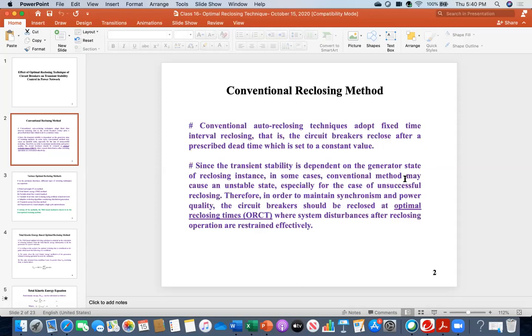Unsuccessful reclosing means the breaker attempted to reclose, but it was observed there was a permanent fault. As discussed before, the fault is still going on, so even though the automated circuit breaker attempts to reclose, it will be reopened again.